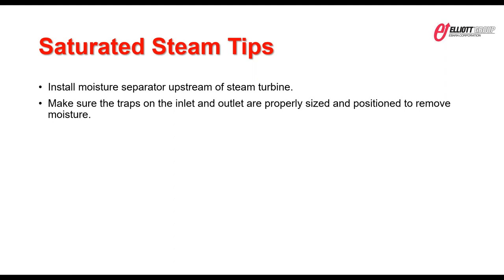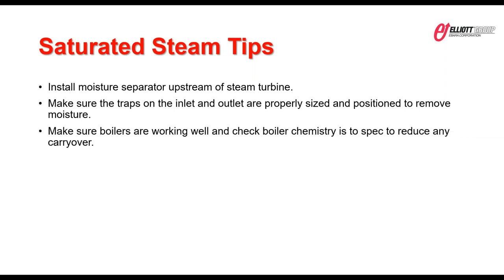Then make sure you have the right number of traps where you need them, and that their position is proper, on the inlet and outlet of the turbine, so that you can drain out any condensate that may be present. From a boiler standpoint, you're looking at the boiler makeup water chemistry, making sure it's clean water essentially and up to spec, so it's not going to have any carryover downstream and affect the turbine or any other equipment that may be downstream.